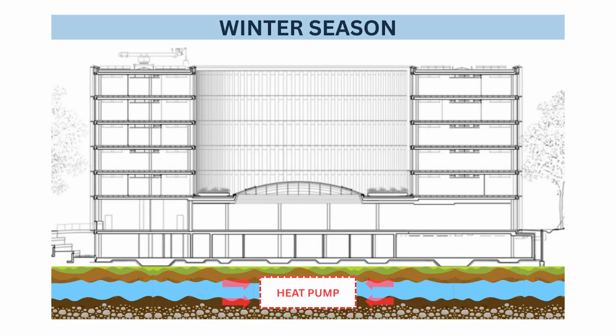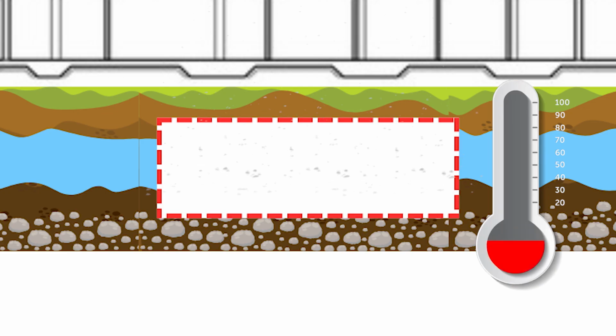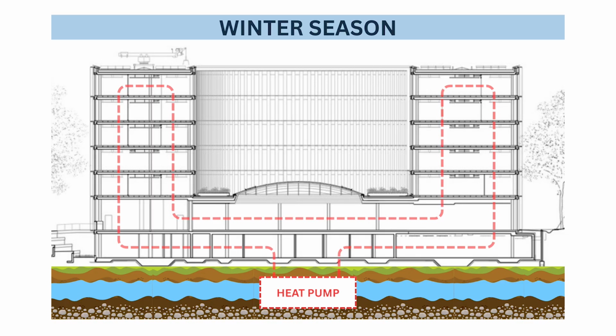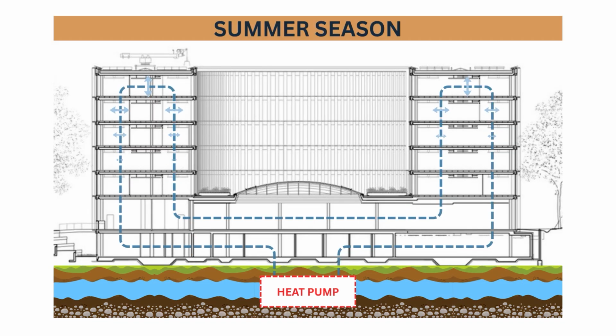In winter, the pump extracts heat from groundwater. That water passes through a heat exchanger inside the heat pump. A refrigerant fluid absorbs the heat and evaporates into gas. This gas is then compressed, raising its temperature. The heat is transferred into water circuits that flow through thermally activated concrete slabs and radiant ceilings, gently warming the spaces above. In summer, the process reverses. The pumps remove heat from the building and send it back underground. When outside temperatures are mild, the system can even bypass the compressor entirely, circulating cool groundwater directly for free cooling.